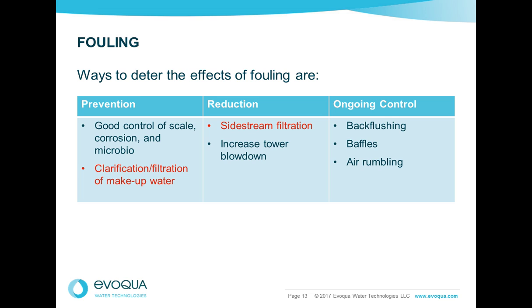Ways to prevent fouling: you can feed a dispersant, and use a good scale or corrosion control program. Clarify the makeup water. The cleaner the water you put into the system, the cleaner the recirculating water is going to be, because everything that you put into the system concentrates up. Another way to control dirt in the system is sidestream filtration. And I think sidestream filtration is just the best thing you can do to make a cooling system operate much better.